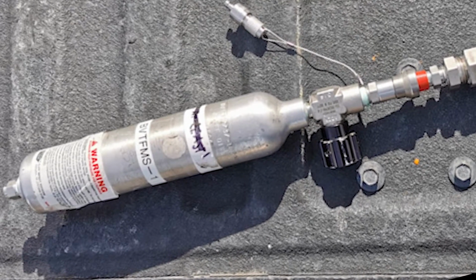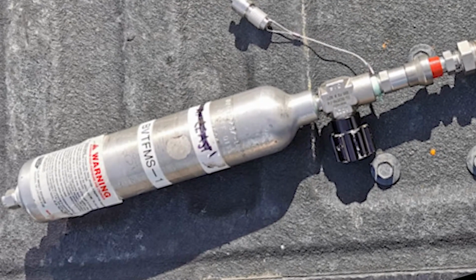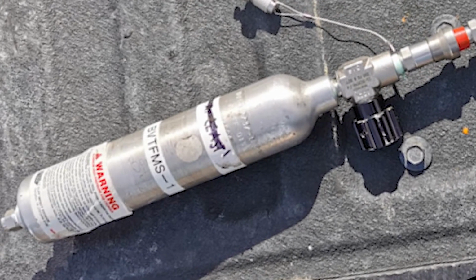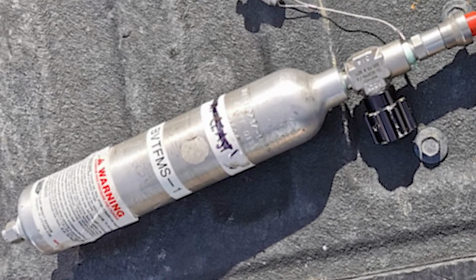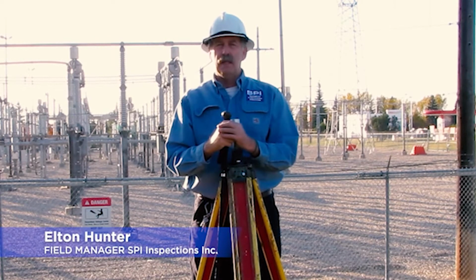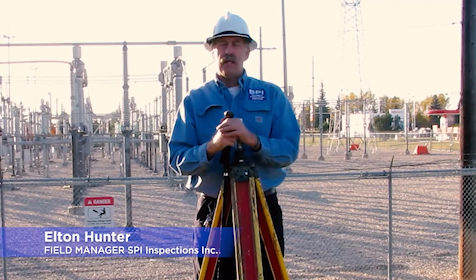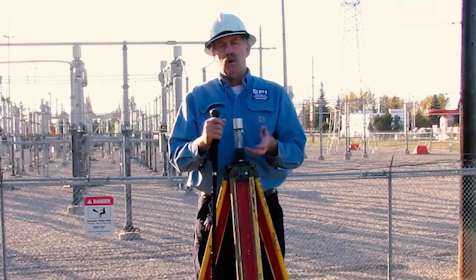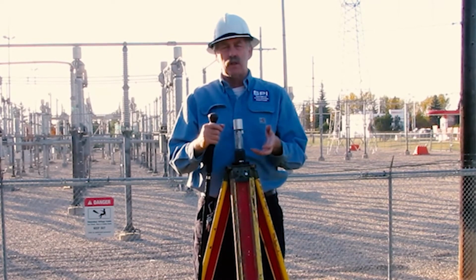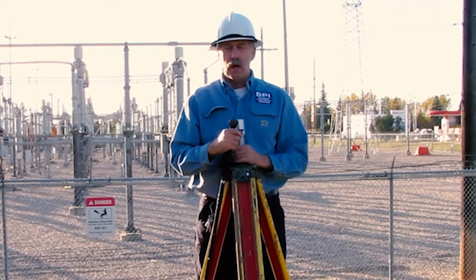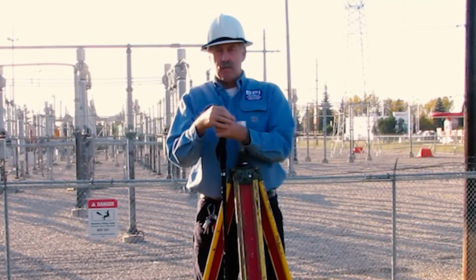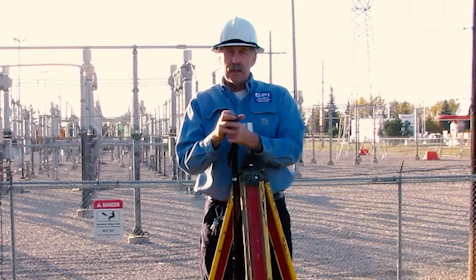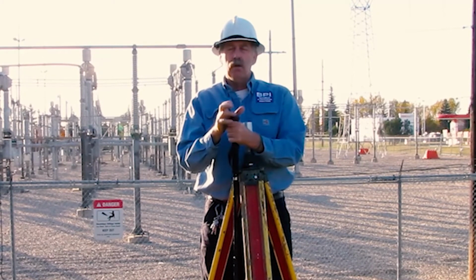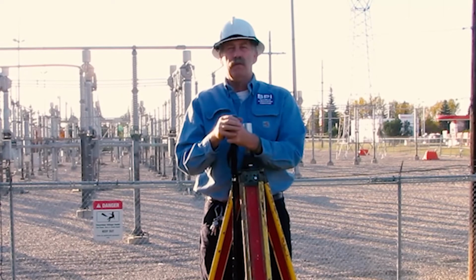We did discover that the gas detection should be done on a calm day, and the operator needs to be conscious of the background behind the leak. A small leak can be difficult to detect. We found it advantageous to mount the camera on a tripod, which helps with longer video timings and steadying the camera. One of the valuable lessons we learned with the GF77 is when we're in video mode and we want to record something over the long term, use a good commercial tripod, or use a monopod to hold it in place when you're standing up there and holding it in place. You get a really crisp, clear picture of what you're looking at, and it makes it much better video quality.